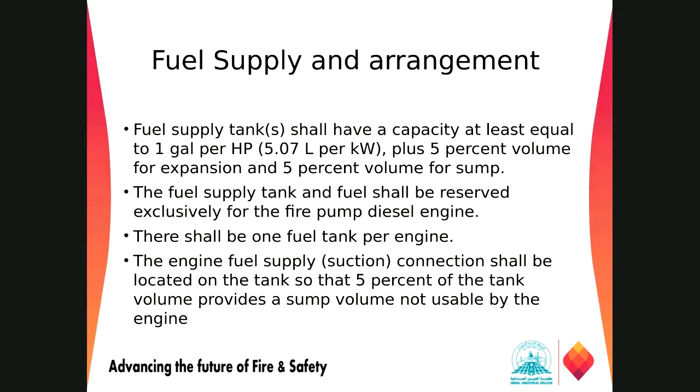The fuel supply and arrangement capacity, we did some calculation in the fire protection design, right? It should be sized as 1 gallon per horsepower plus 5% for expansion and 5% for the sump, right? And there should be separate fuel supply lines for each diesel engine, and there shall be one fuel tank per engine. And all those requirements we discussed in the beginning, we have to calculate based on NFPA 20, the size, quantity, and all.